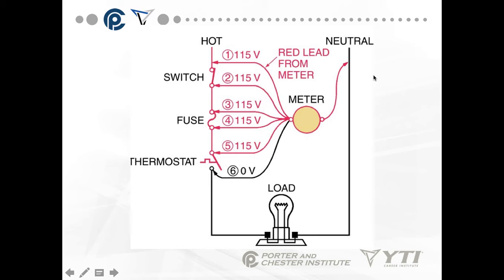Between 5 and neutral I have 115 volts. Now at 6 and neutral I have 0 volts. My next step would be to move this lead from neutral and put it on point 5. My voltage across that open switch would be 115 volts.